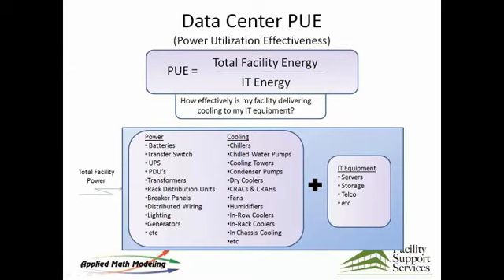So if we assume a COP of 1.8, which, by the way, is not unusual, I have seen them as low as 1. Remember that 1 would mean that for every kilowatt of power going to the IT equipment, it's taking me another kilowatt to pump that heat out of the room. Very poor, but not unusual. That would drive the PUE to be 1.6, or the DCiE to be 63%. RTI here is 59, almost 60%.